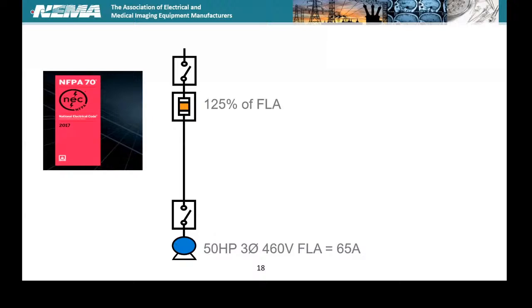So we're going to look at this motor here, and we've got a 50 horsepower, 460 volts motor. We've got a full load amp of 65, and we know that the conductors are sized at 125%. But if we start looking at overload, we are allowed to go 125% under these conditions of service factor and temperature rise and stuff like that. We can go up to 125% under the general rules for overload protection, so we can't exceed that amount. So 65 amps times 1.25 gives us 81.25 amps, and an 80 amp Class J fuse would fit the bill. It meets the overload protection, and will it meet the short circuit protection?